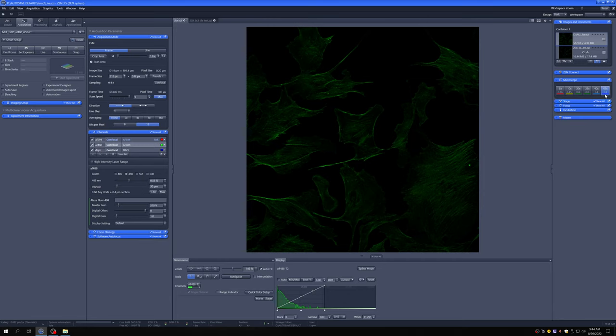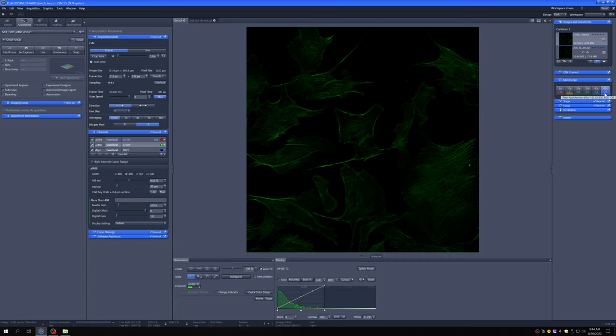And then we have the 40x and the 63x 1.4 objectives. These are both excellent objectives for subcellular work. They have the same numerical aperture, so even though they have different magnifications, the 63x is not higher resolution. They both have the same resolution. The 40x obviously has a bigger field of view.